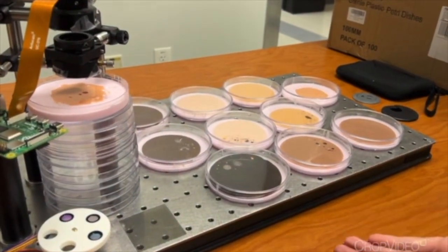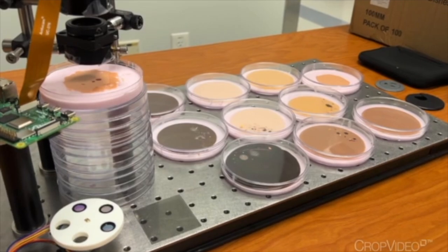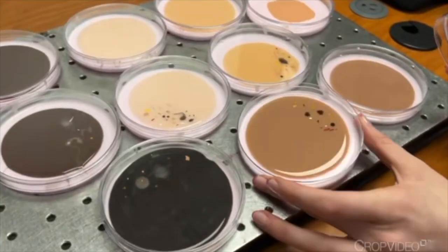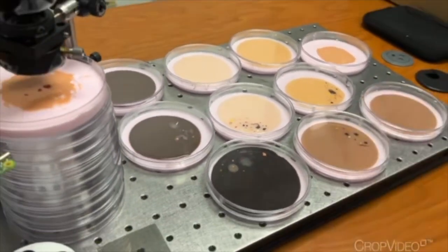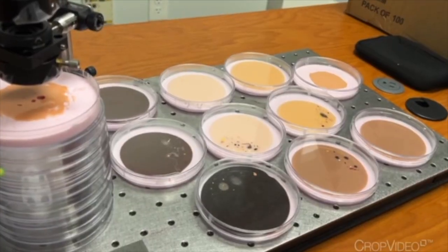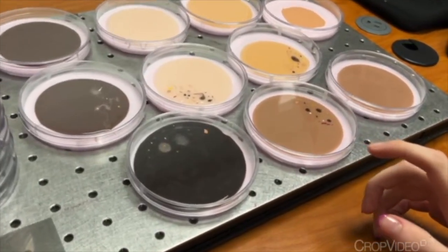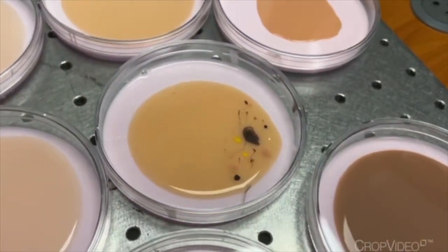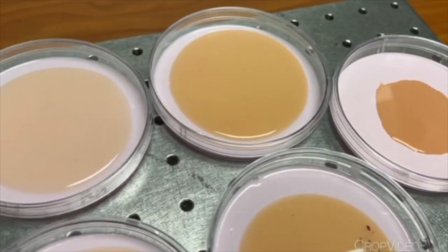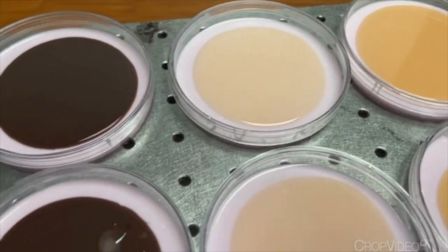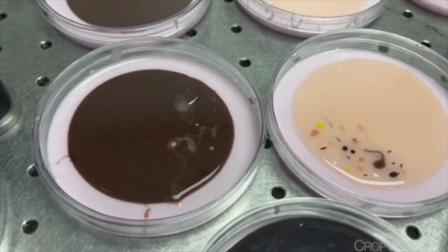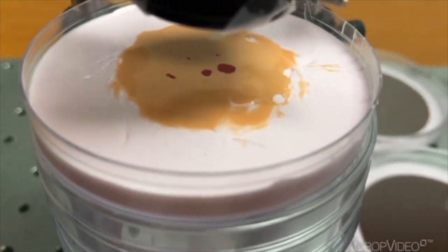So here we created a set of layered silicone phantoms to use in place of live subjects for our preliminary testing. So this is one of them here. The phantoms shown here in the petri dishes all represent different skin tones that we controlled by adjusting the amounts of silicone pigments and titanium dioxide mixed in to mimic the light scattering that occurs within human skin. Each phantom was cast in a 9.5 centimeter diameter petri dish and contains a thin pigmented epidermis layer between approximately 0.3 and 1.2 millimeters thick.